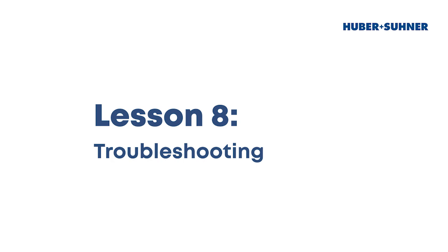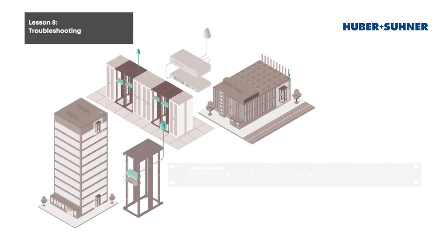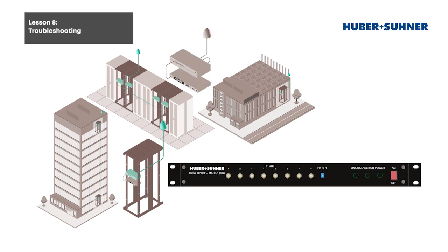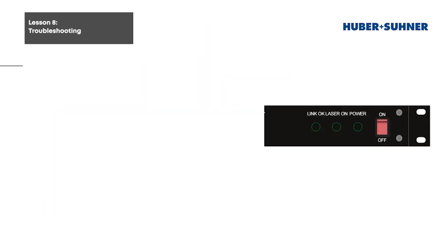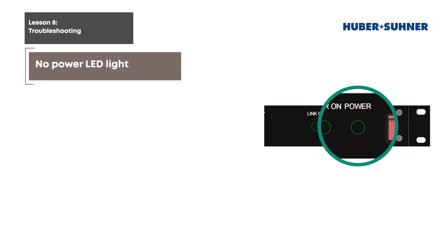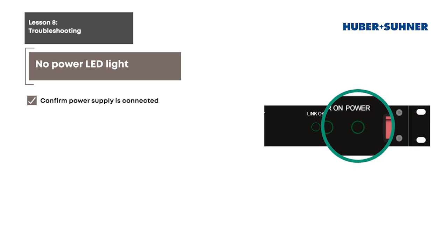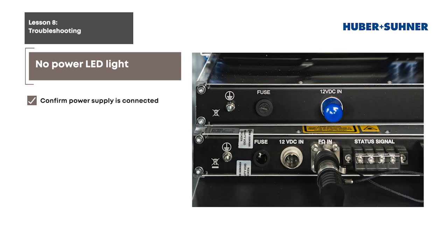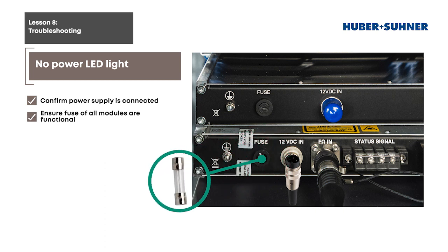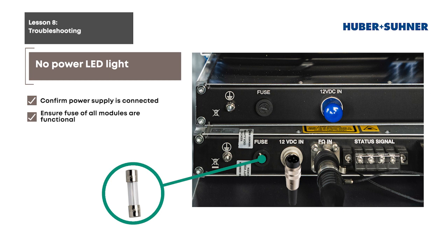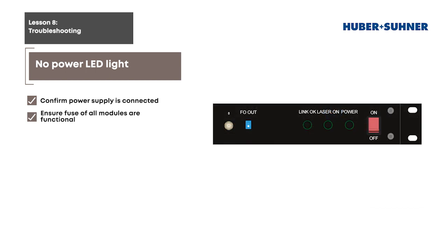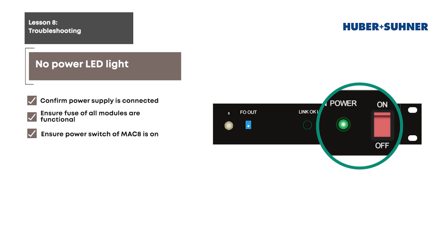Lesson 8. Troubleshooting. With any installation, we recognize there may be a need for troubleshooting, which is why we prepared the following common troubleshooting measures. If there is no power LED light, make sure the power supply is connected. If a DC-DC converter module is used to power up the receiver, then make sure its power supply is also working. Ensure the fuse of all modules are functional. If not, replace according to the specifications listed in the installation manual. And finally, check that the power switch is in the on position.